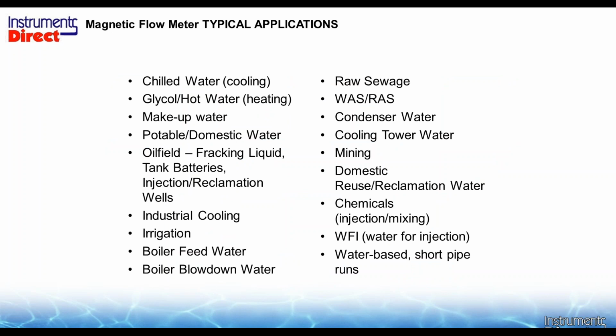So where, again, do we use magnetic flow meters? Before we said any water-based applications, and just to get your brain on the same track as mine here, which is probably impossible because you've never met my brain before. Typical applications, anything that's got the word water next to it is fabulous. So chilled water applications, hot water applications, glycol. Well, glycol is not conductive, but if you get more than 50% water, then we don't really care. So we'll understand if you have a majority amount of water with a mixture applications, it's usually not that problem.